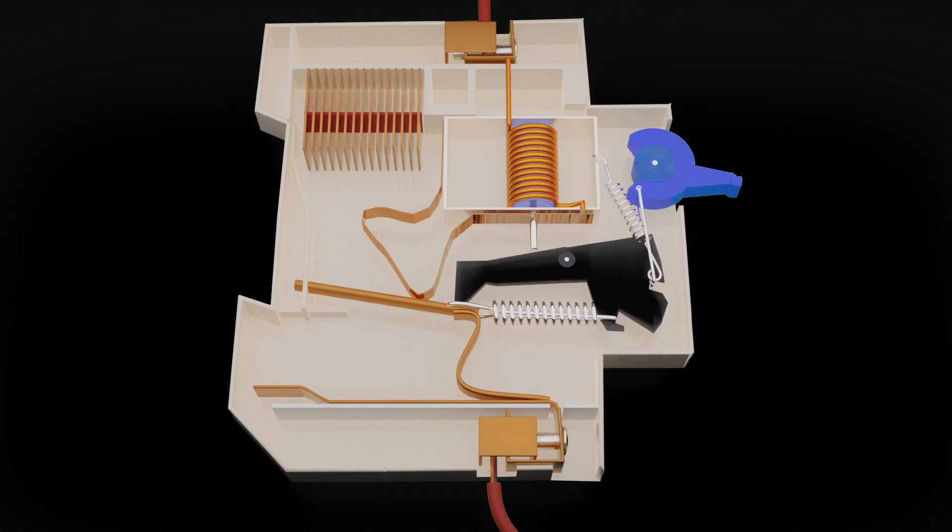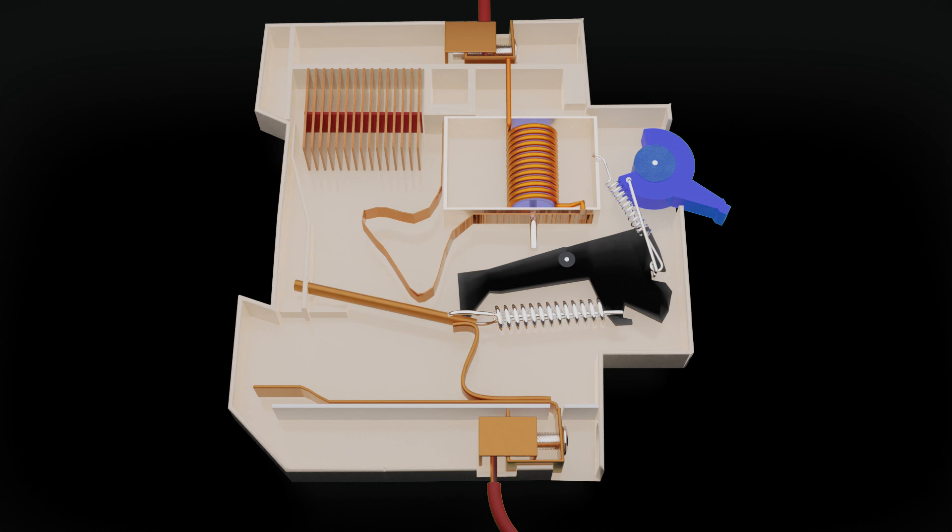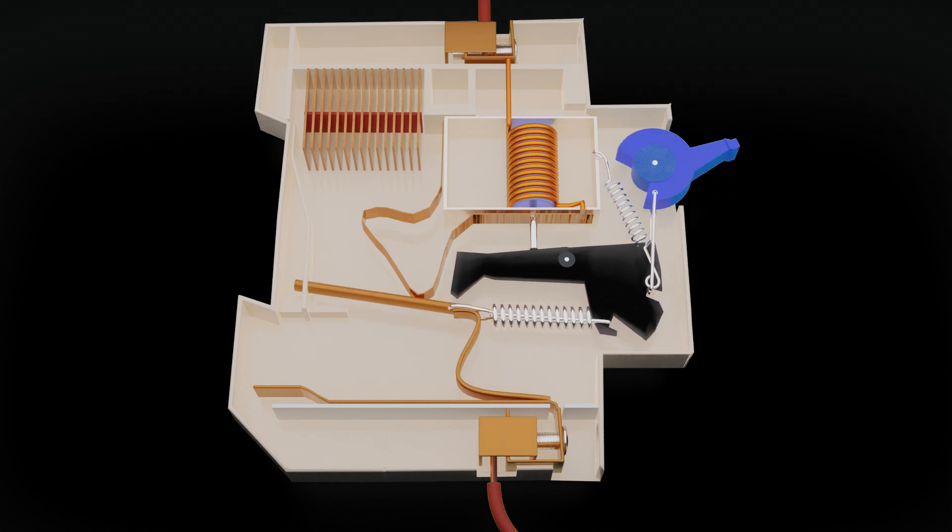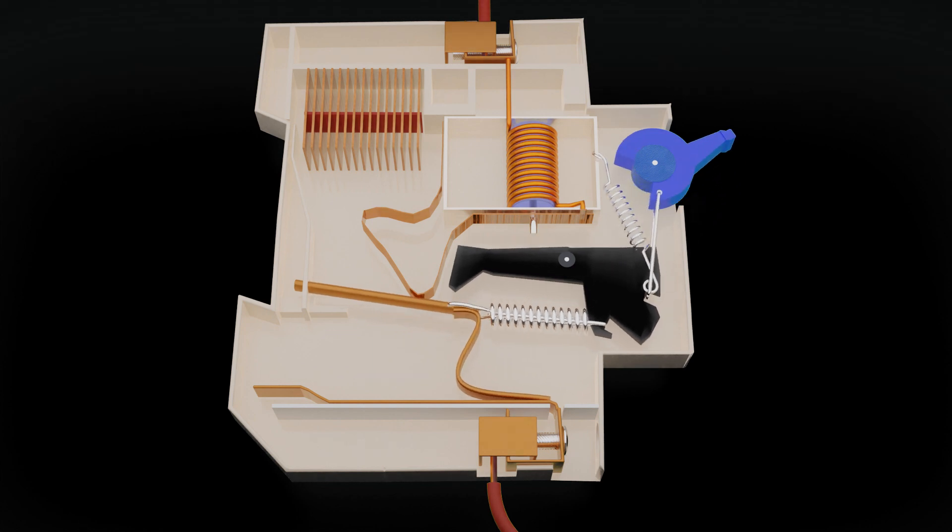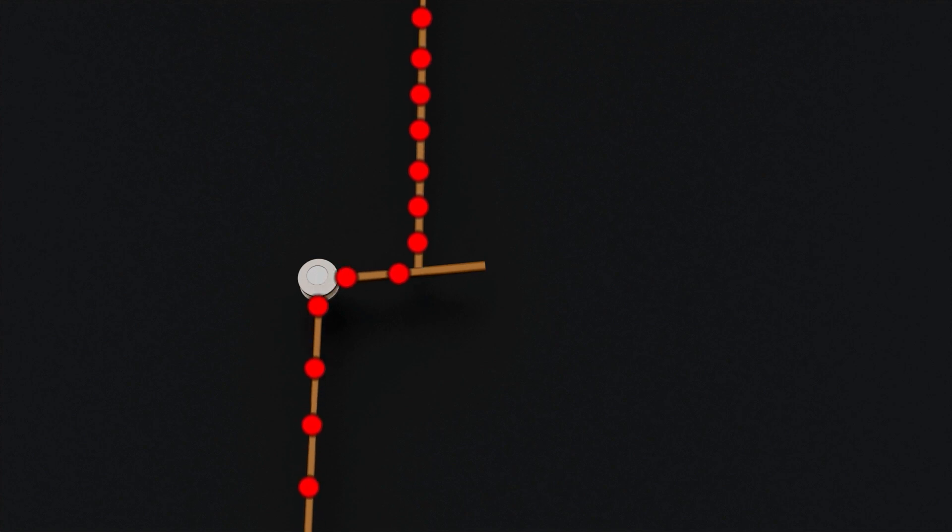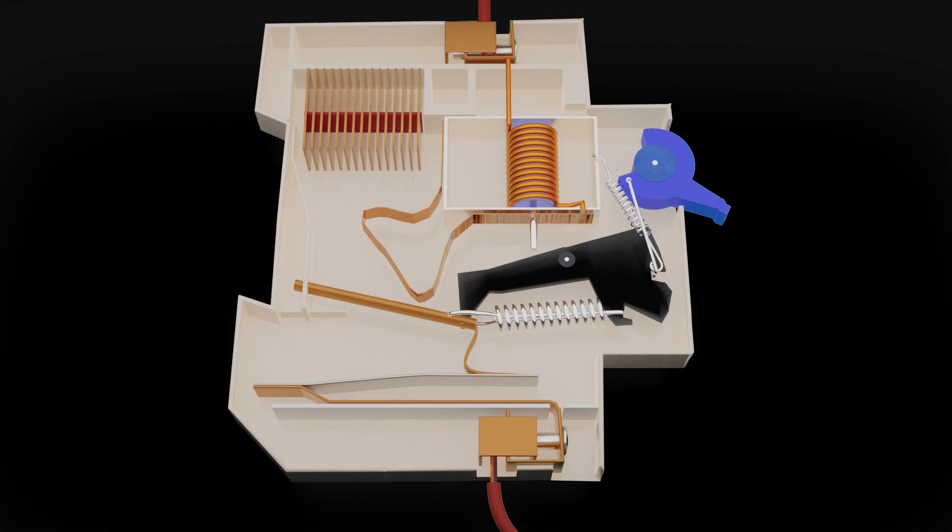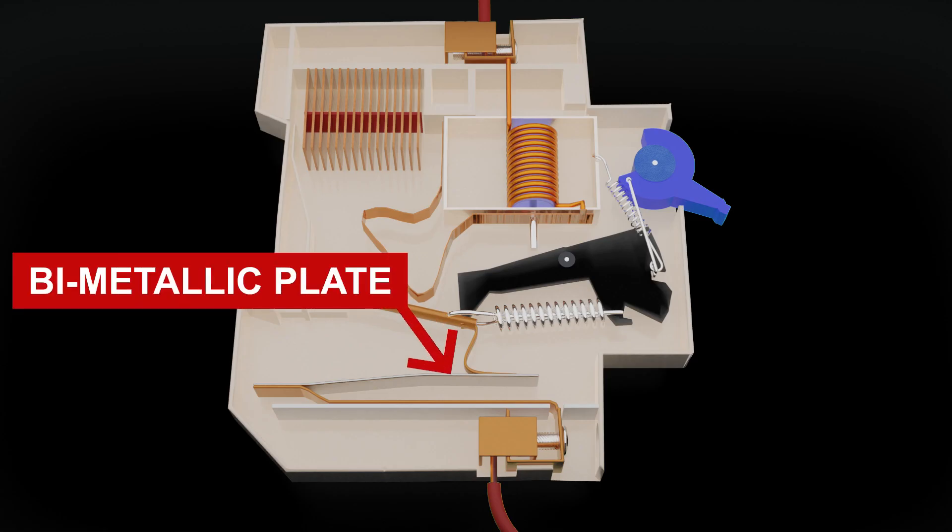So friends, it is possible to automatically protect from short circuit using this mechanism. Apart from short circuit, one more problem—overload—can be solved with this MCB. In overload condition, the current flow in the circuit also increases, but not as much as in short circuit. Bimetallic plate is used in MCB to solve this problem. If too much current flows through the bimetallic plate, it heats up and bends, and as a result, the connection breaks.